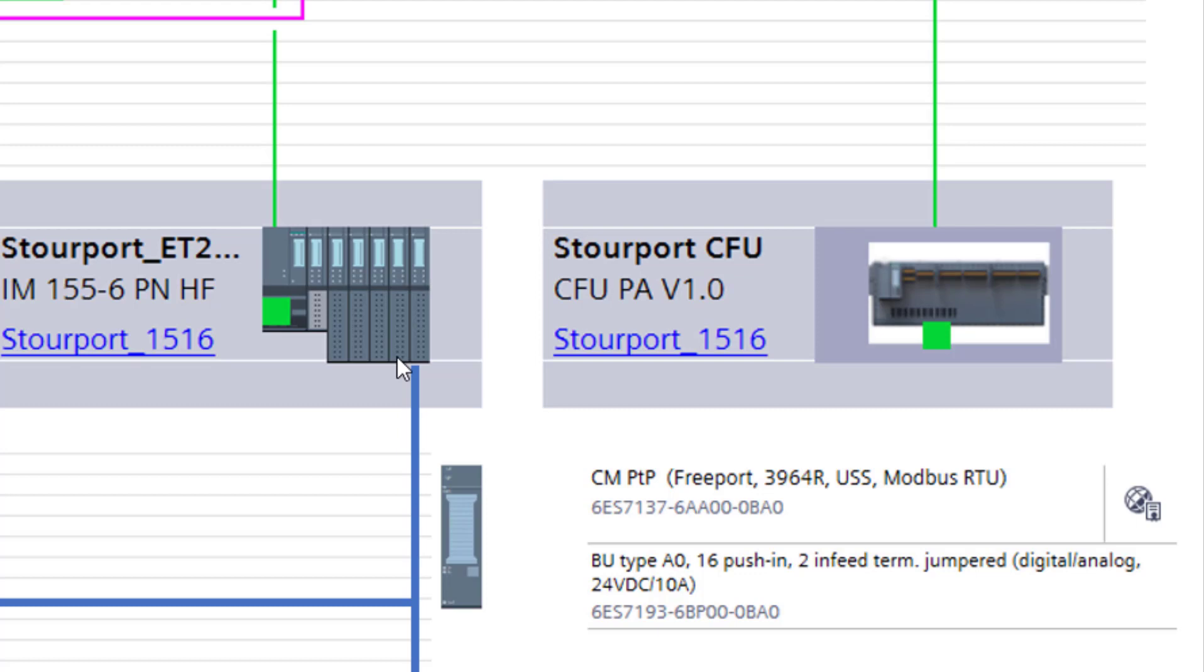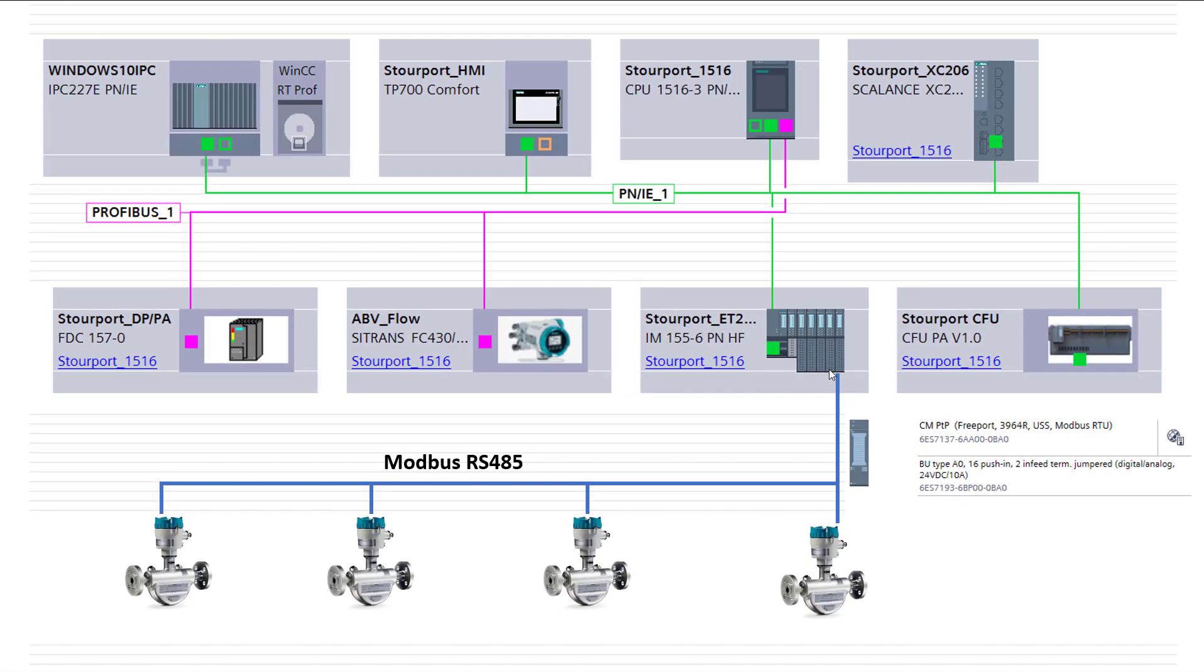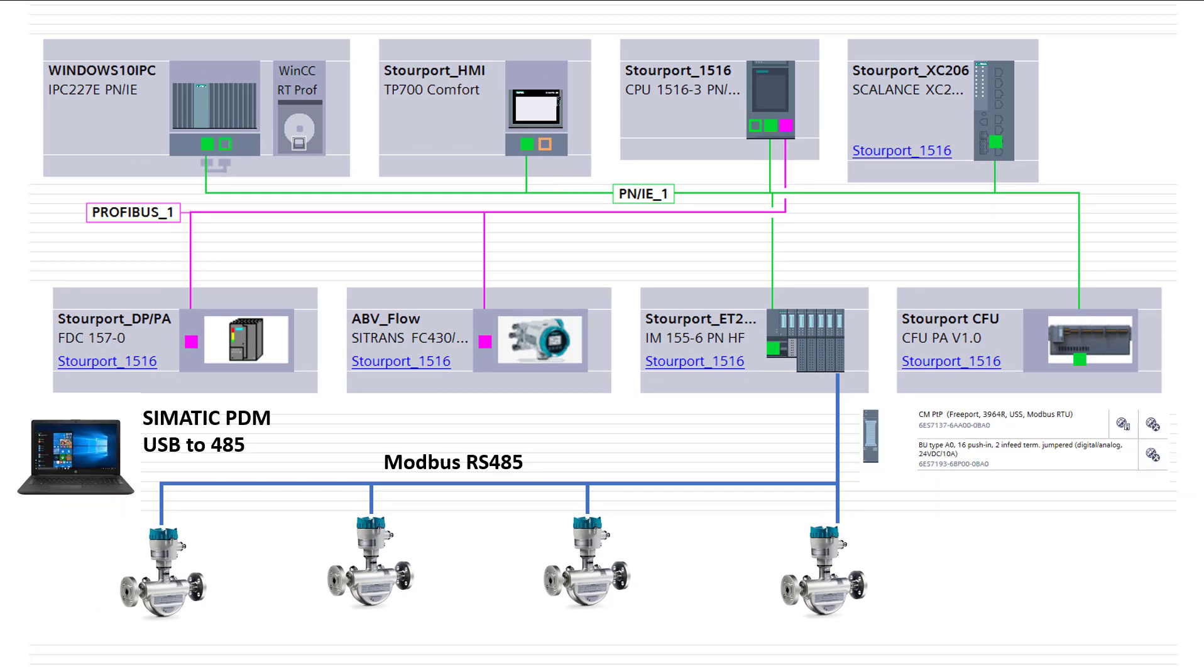The issue occurs with Modbus when you have a problem on site. If we really need to do a deep diagnostic delve into what's going on with the Coriolis meter, then we need to connect SIMATIC PDM.